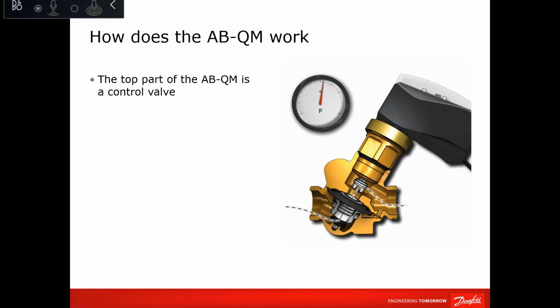And if the pressure is increasing, the sensing point at the exit of the valve will be pulling the membrane down to make this cone go to closed position. When the pressure is reducing back, there is a counterbalance sensing point inside this hollow cone, and the spring will bring back the cone to its initial position. So it's not as complicated as it looks, but in order to make the valve compact, it's this way. So in our case, we'll see on the cut piece later also.